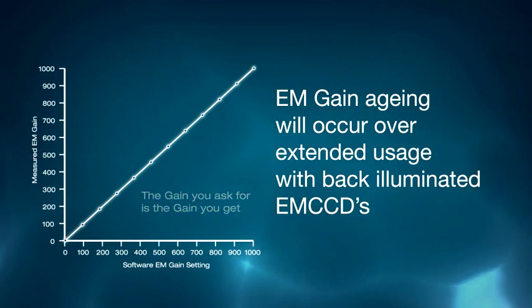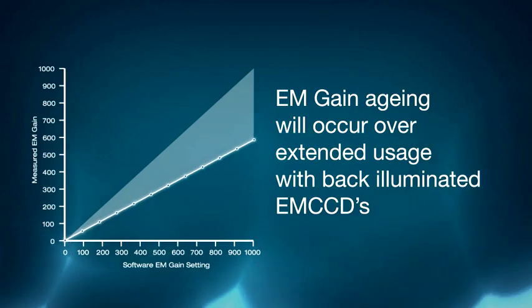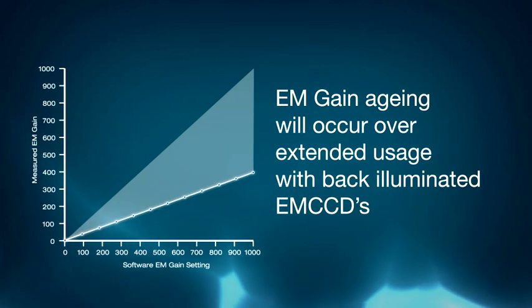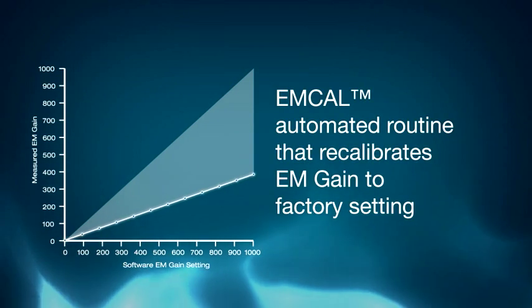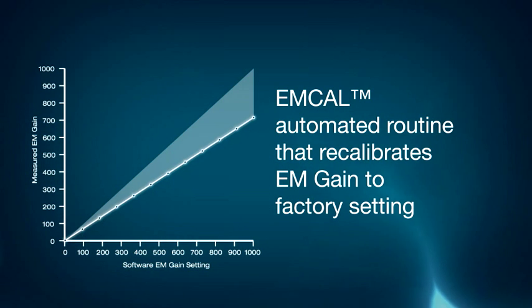Also integral to iXon Plus, EMCAL is Andor's unique patented solution to the phenomenon of EM gain aging in back-illuminated EMCCDs — a process whereby the EM gain multiplication factor progressively falls off over extended use.